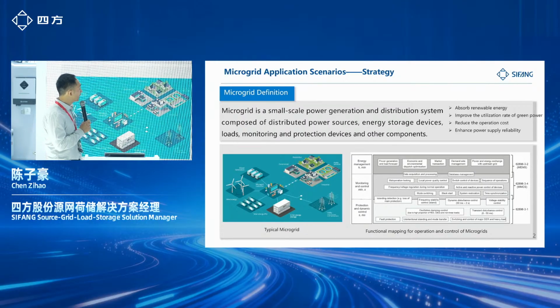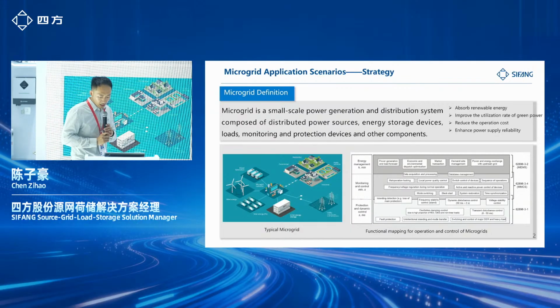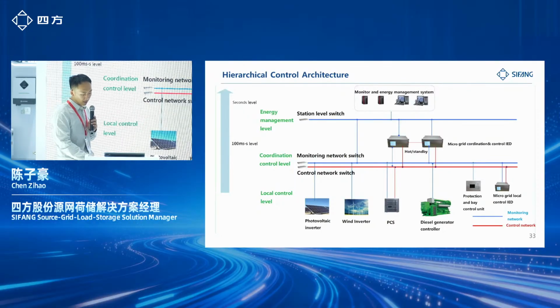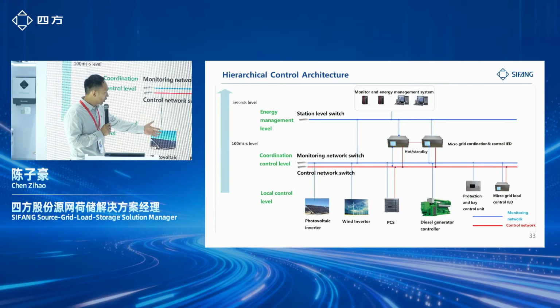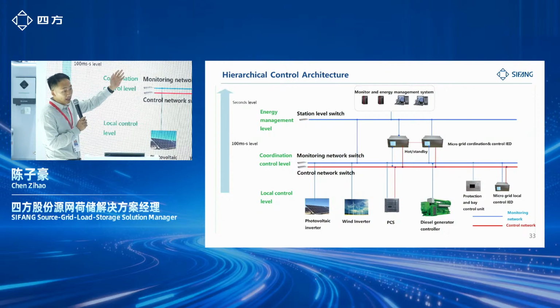And here shows the typical composition of the microgrid. And the Sifang company applies the whole solution complying with the IEC standard, covering the planning, grid connection, control, and protection. And we also use this three-layer architecture. The main level responds to the dispatching command. The second level is for the rapid control, and the local level is for the equipment level to achieve this millisecond response to the system change. And what we can provide first is our EMS platform.